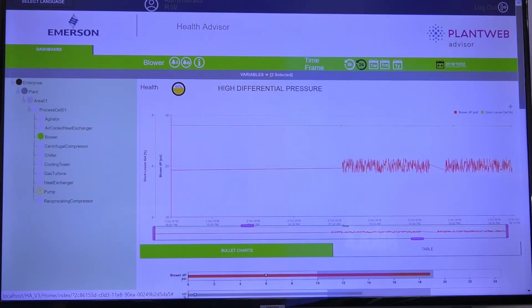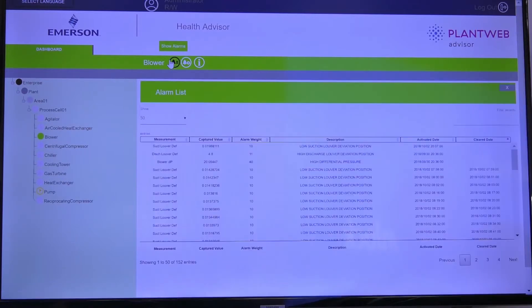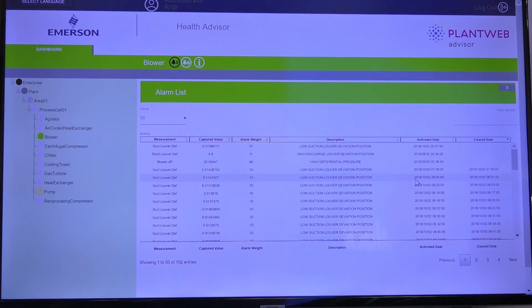The application provides the ability to capture a baseline when the equipment is working clean and normally. Then future operation is compared to that baseline to determine a health indicator. The asset health is a combination of all active alerts and the distance from the standard baseline conditions. An overall health index for each unit and area is calculated from the asset health and its criticality.